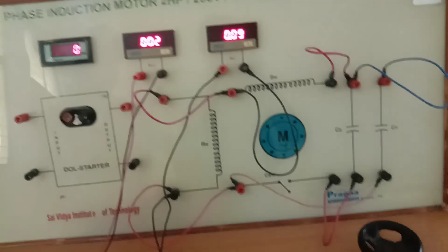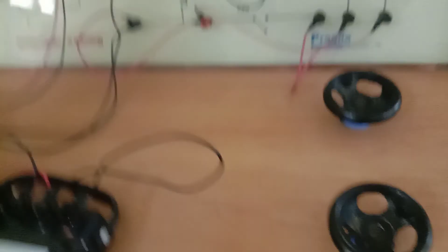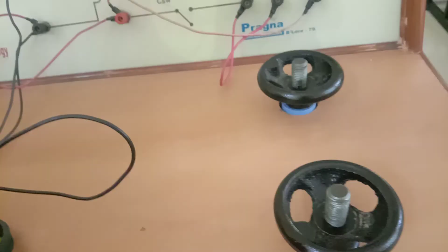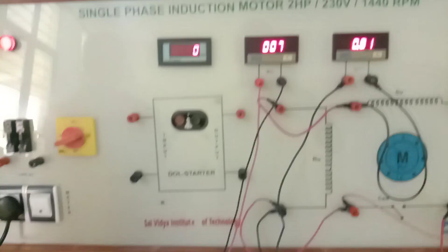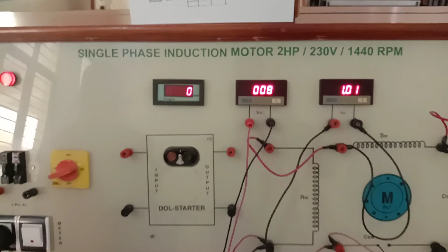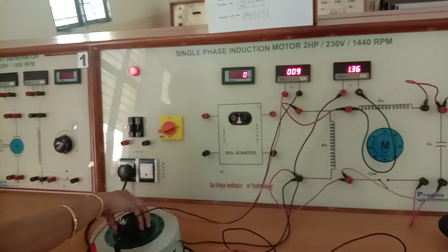Now since the auto transformer is in minimum position, vary this such that the ammeter reaches the rated value. Before that, we have to ensure the rotor is locked. Once the rotor is locked, we can start to apply the rated value of the current by varying the auto transformer. So what is the rated current here? It will be around 12 amperes, so we can vary up to 11.5.